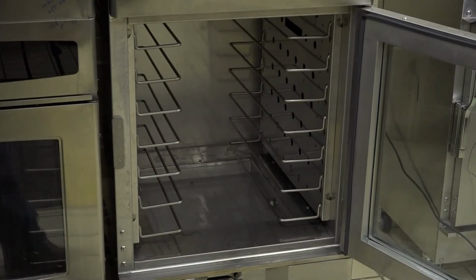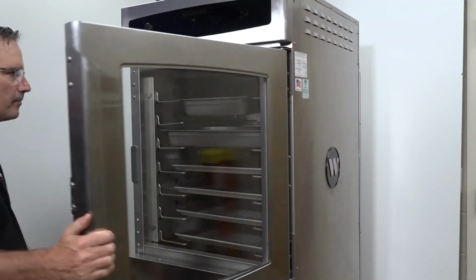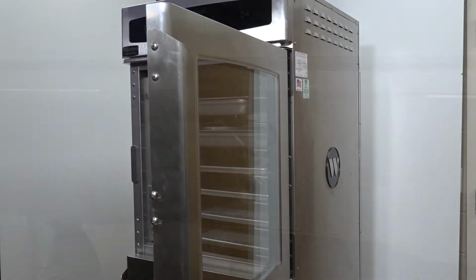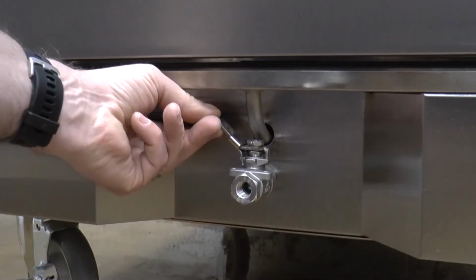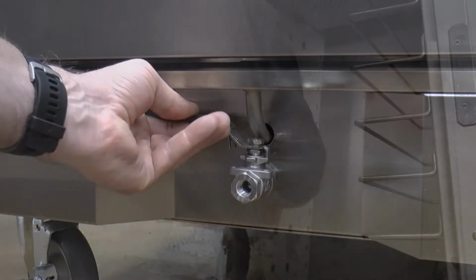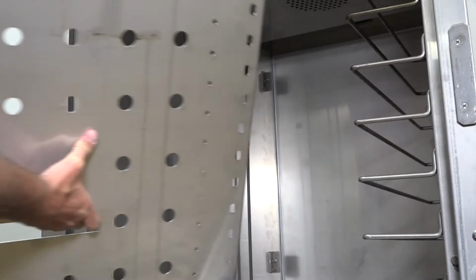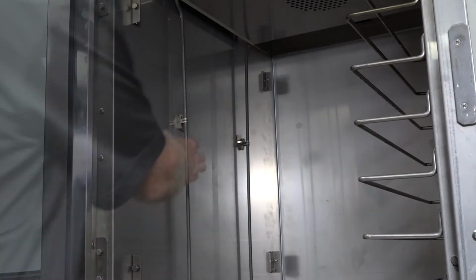Inspect the doors. Ensure that the handle and hinges are secure. Ensure that the doors are aligned correctly. Adjust the doors if necessary. Inspect the drain valve for any leaks. Remove heater covers and ensure that all heaters are clean and secure.